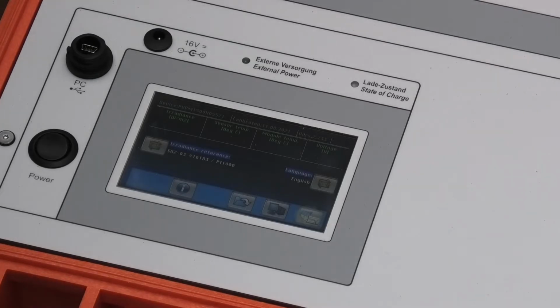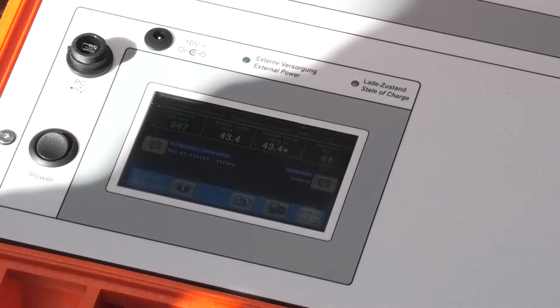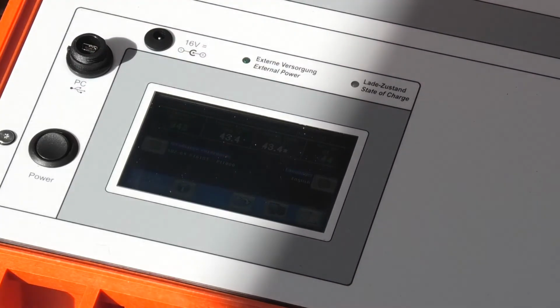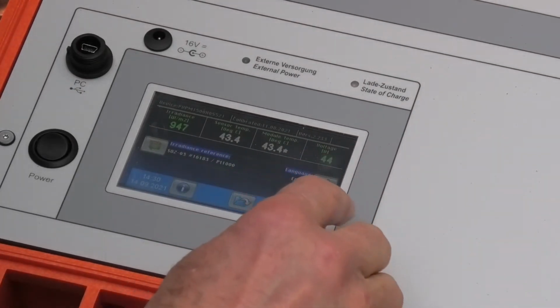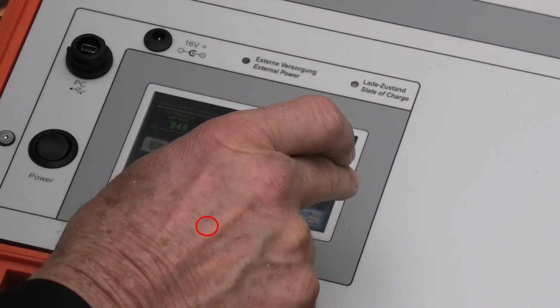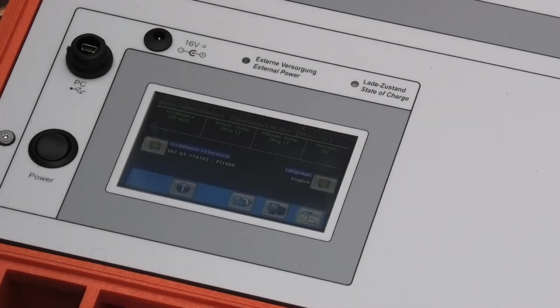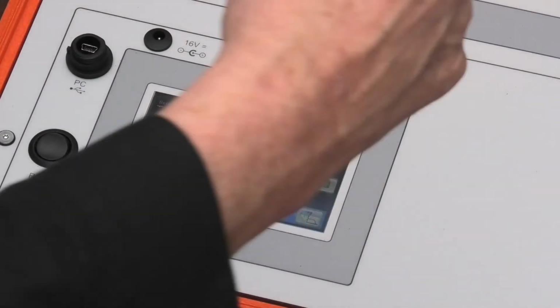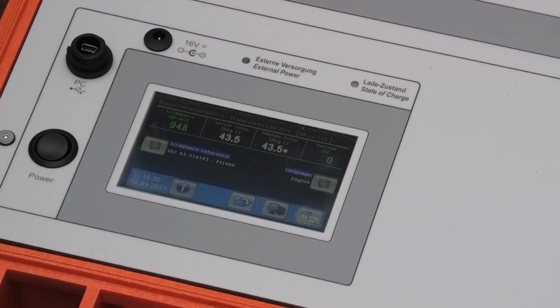Now, one of the things, I'm going to obscure this panel now, so there'll be 3 tests on it. When I obscure the panel, I'm just sticking something to the front of the panel to cause a discontinuity, as if we've got a failed panel. So here we go. Here I simply go to test. There we go. So those three measurements have now been stored. I switch the isolator to off, and I can now disconnect the instrument, and it's safe.